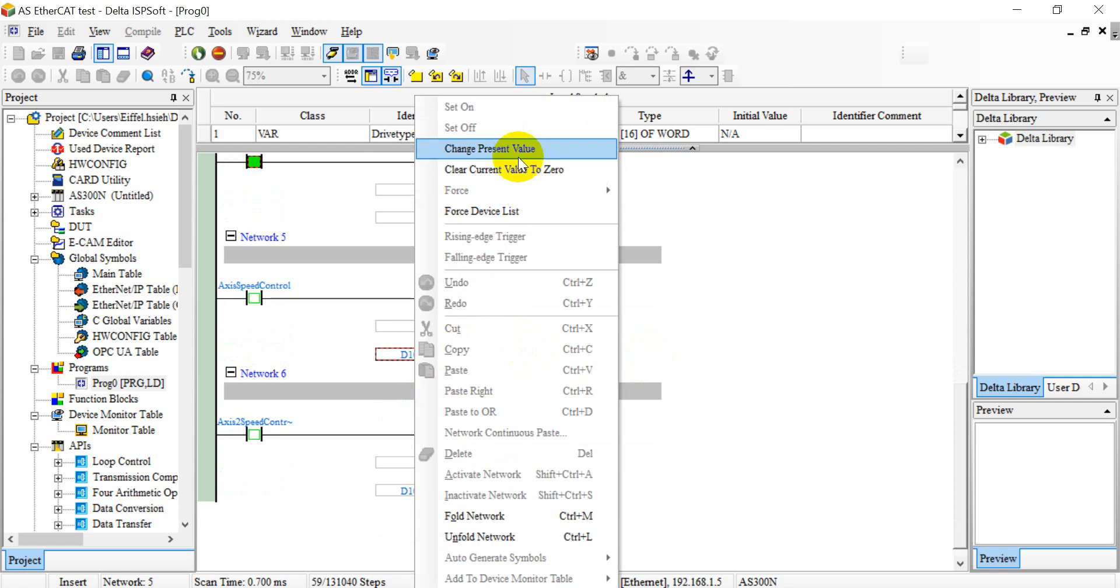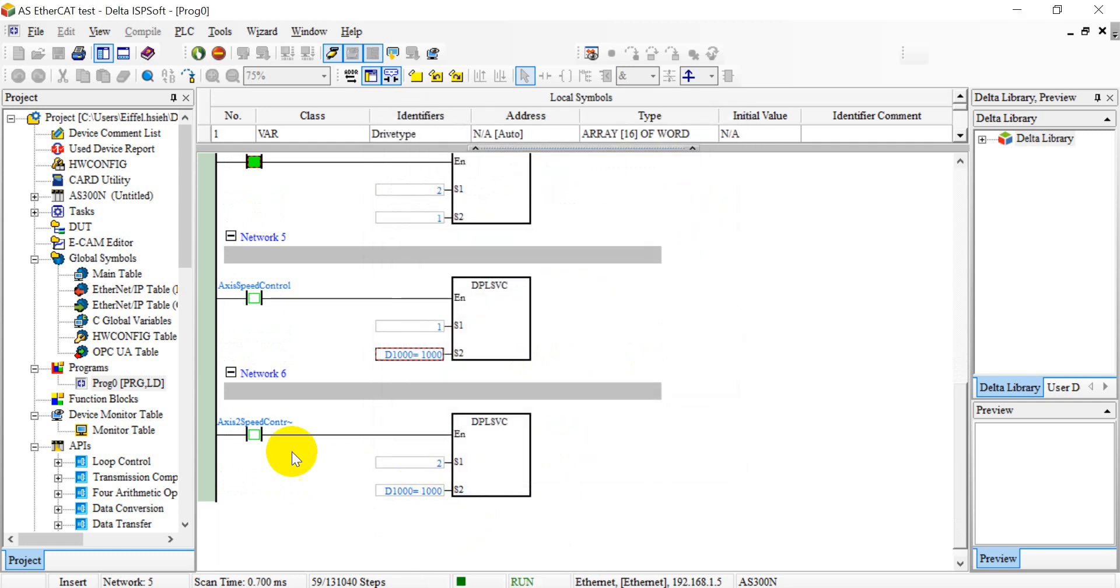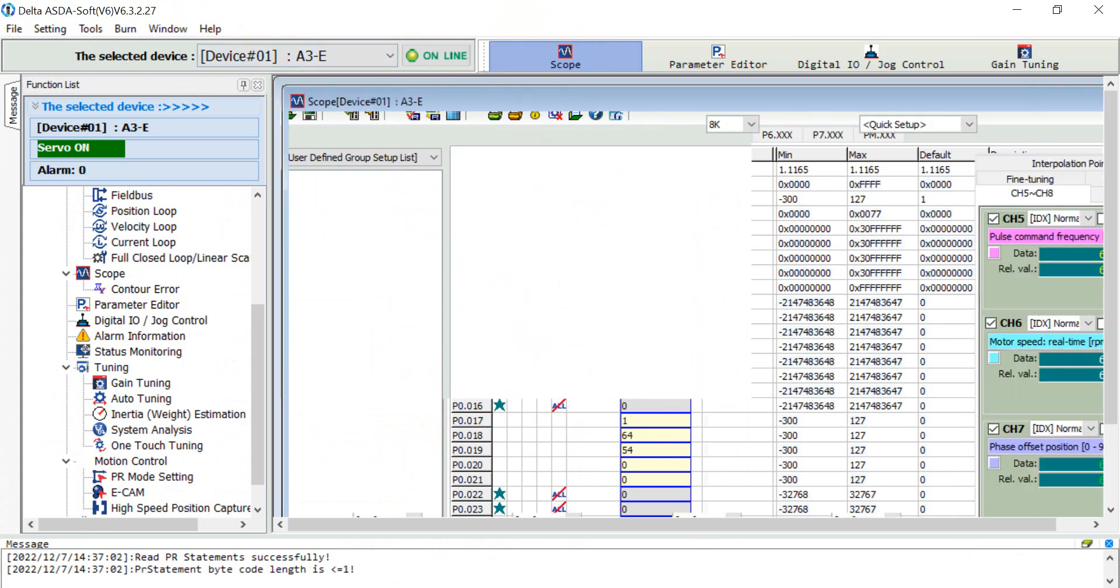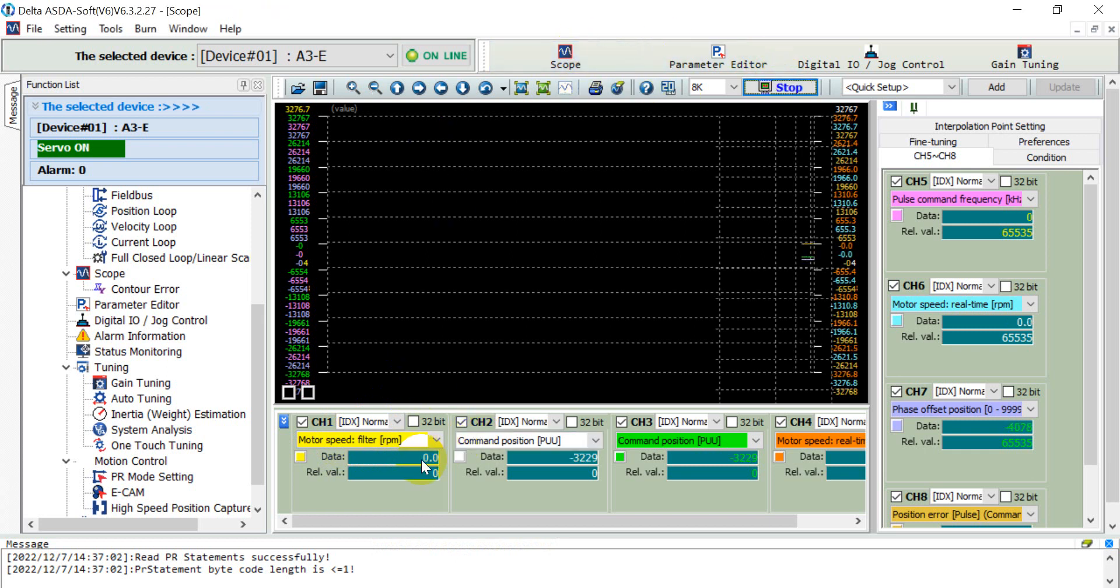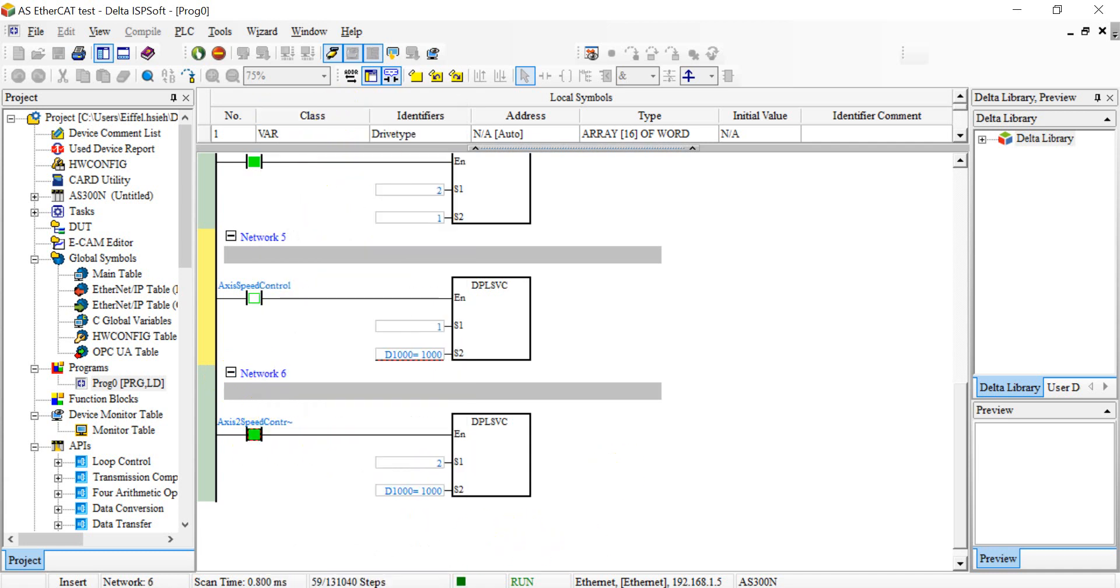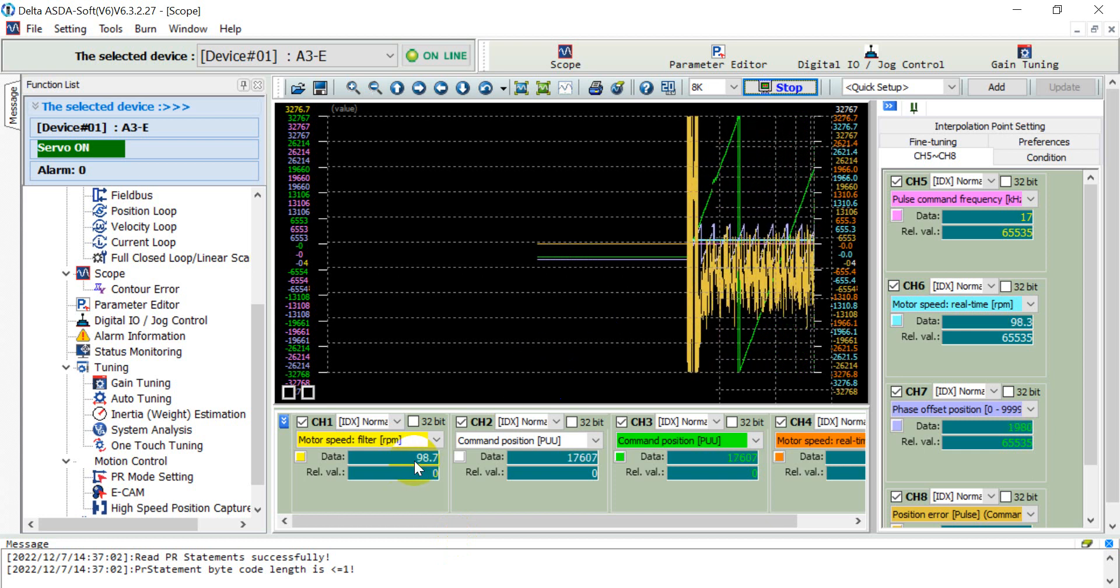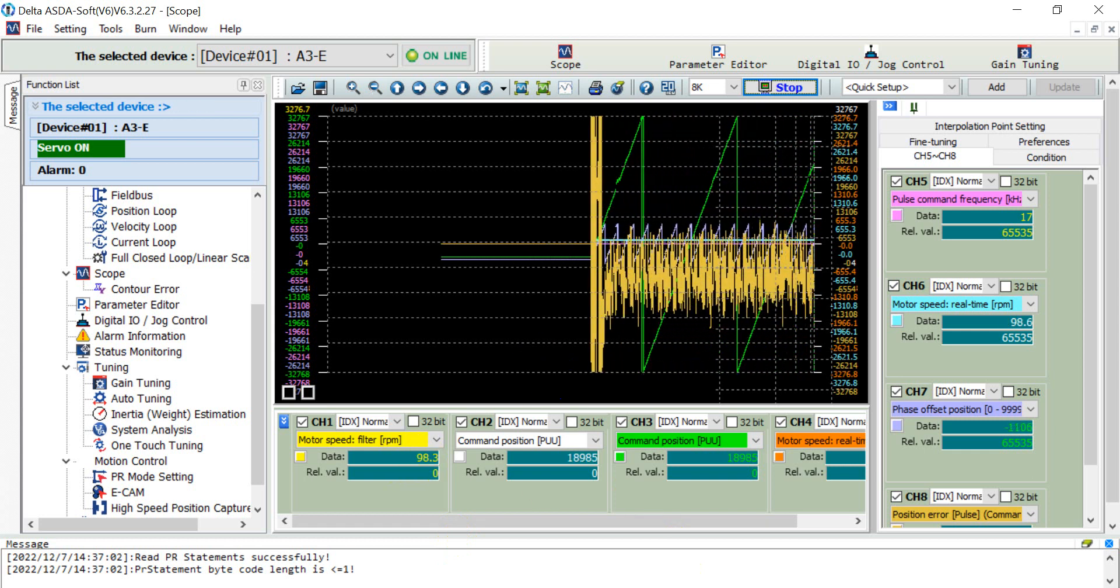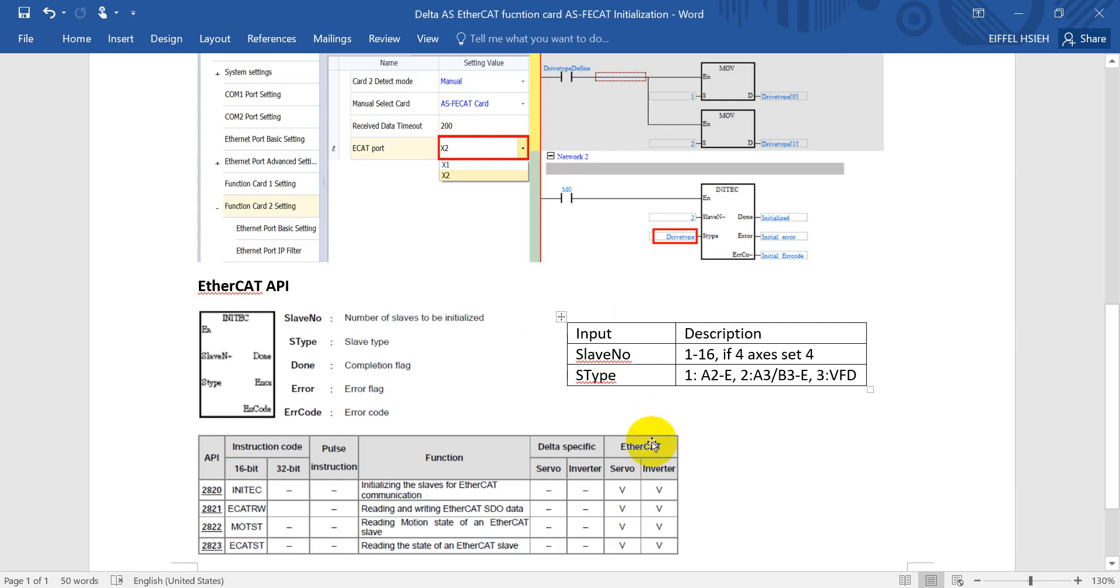Next I will show you we monitor the speed from ASDASoft. Here we keep 1000, so that means the speed at the driver motor side will be 100 RPM. Now we can switch to ASDASoft and click the scope function. Follow the first channel which selects motor speed and run. You can see now it's at zero. Later we go back to the PLC program and then enable this. Then we can go back to check. You can see the speed is around 100 RPM.